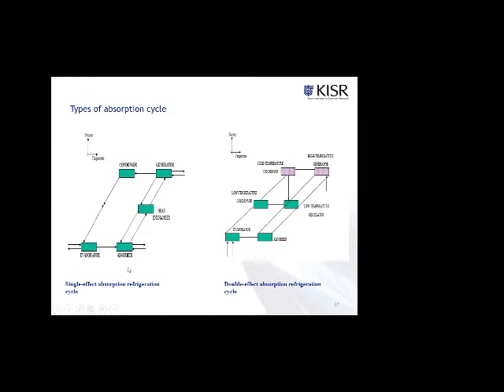This thermal compressor usually combines three components: the generator, the heat exchanger, and the absorber. You see that here we don't have a compressor. We have an evaporator, a condenser, and of course an expansion valve, but we have a generator and an absorber, and of course a heat exchanger in between to use the excess heat in the system to heat the fluid that's going up to the generator to save energy.